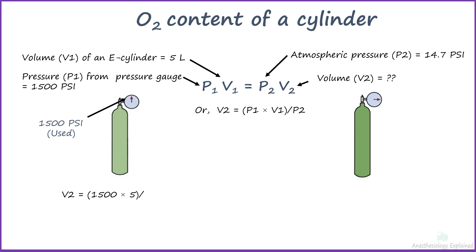Replacing with values, V2 equals 1500 into 5 divided by 14.7, which equals 510 liters. An E-cylinder with the pressure gauge reading of 1500 psi contains 510 liters of oxygen.